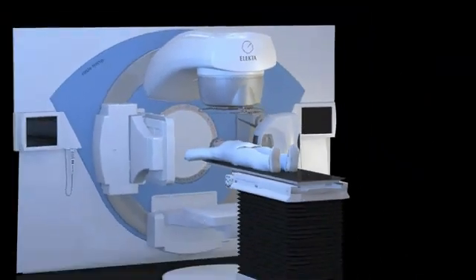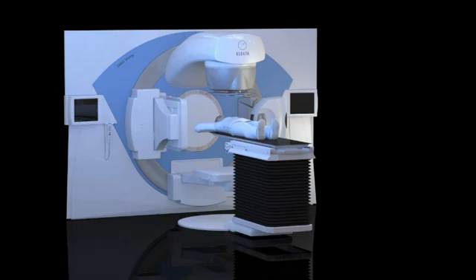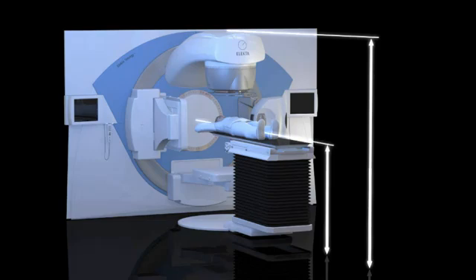This slalom bending is unique to Elekta linear accelerators. It helps to minimize the size of the machine and ensures that its isocenter remains low, which is important for patient setup.